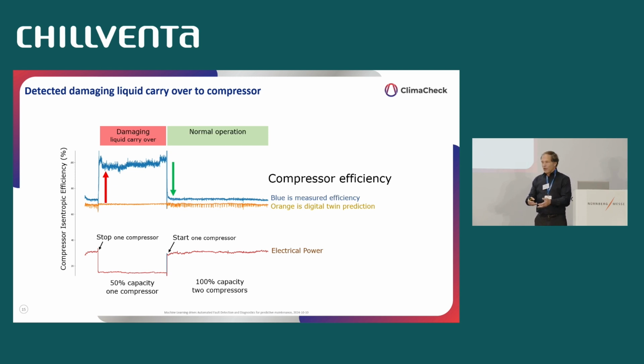That cools down the compressor, so it looks like it's super efficient. Of course, that is a fault. When you cool the compressor, it will damage the lubrication properties of the oil. So that creates failure, maybe one, two months, three months later. But there is a huge amount of compressors failing in Europe every day because of this particular problem.